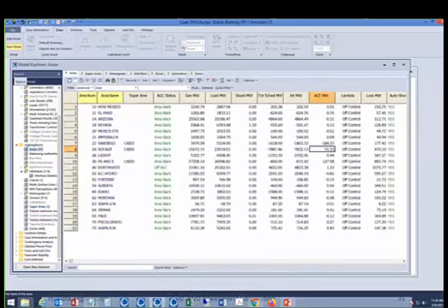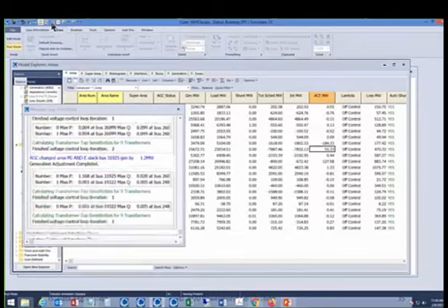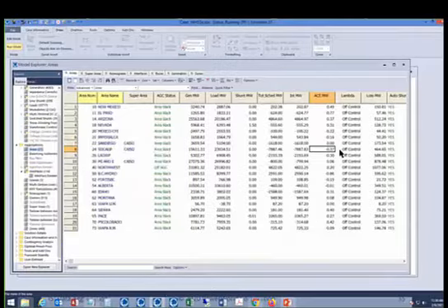But in our case, I just did 200 megawatts. I should be able to undo that by solving the power flow. And yeah, in fact, it does. I don't know if it goes back exactly the way it was before because I'm using areas. I guess it probably should because I'm using area slack with these three. So the whole ACE should go to the same spot.